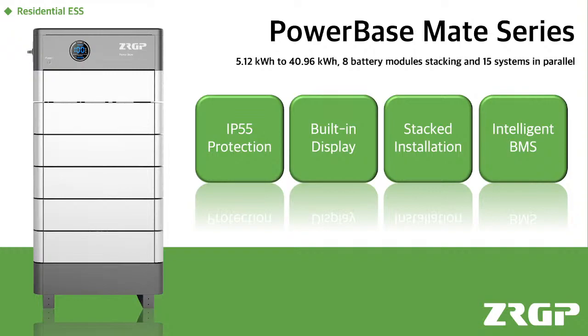With a maximum stacking capacity of 40 kilowatt-hours, the system can also be connected in 15 groups in parallel, and after paralleling, the maximum capacity will be 600 kilowatt-hours. The product has an IP55 protection level, built-in intelligent BMS, and a display screen, which is convenient for users to check system operating information.